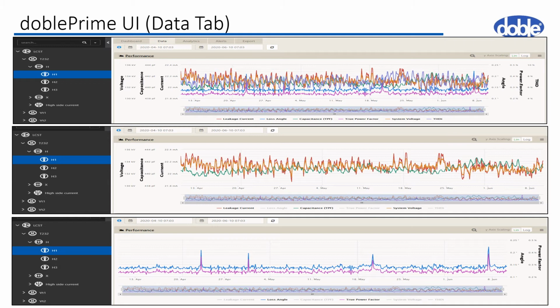This makes sense. The bottom shot, it's known that the power factor or the tan delta is directly related to the loss angle. By turning off primary voltage, leakage current, and capacitance, you now see the true power factor and the angle loss. And you'll notice the patterns follow each other very closely. Again, makes sense.